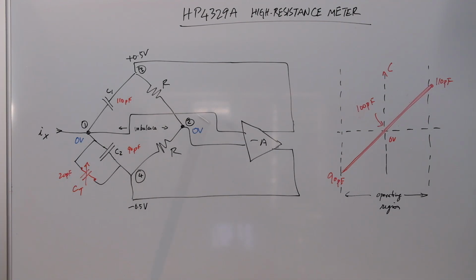So it sets up an oscillation, which is in the hundreds of, I think 100 kilohertz roughly. That amplified signal is then amplified through the amplifier chain, which is then rectified and displayed on the meter. So in order to convert this to a resistance meter, what you need to do is inject another current, which further imbalances the bridge.